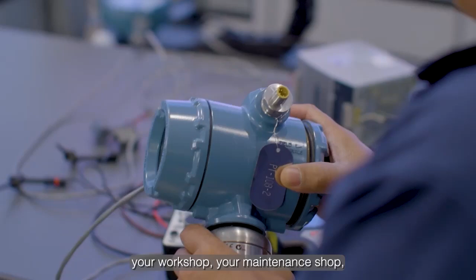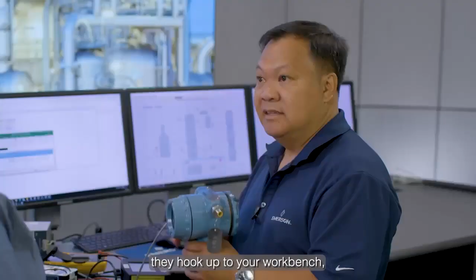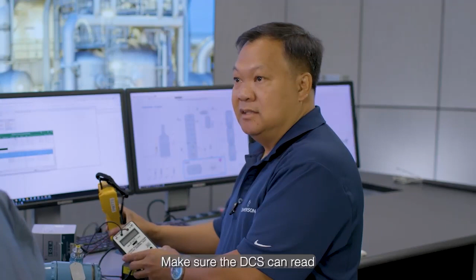Normally, the field instrument will come to your maintenance shop. They hook it up to the workbench with the power supply, then you hook up the field communicator and go through all the parameters the device can have, which could be 40 to a couple hundred parameters. Once that's done, you need a calibrator and the tool to drive the upper and lower range to make sure it's calibrated correctly. Then you send the device to the field to hook up and go through the same procedure, making sure the DCS can read the upper and lower range properly.